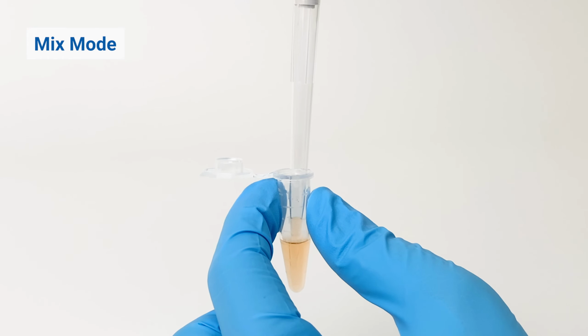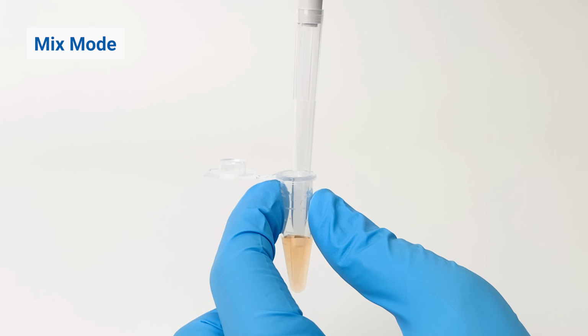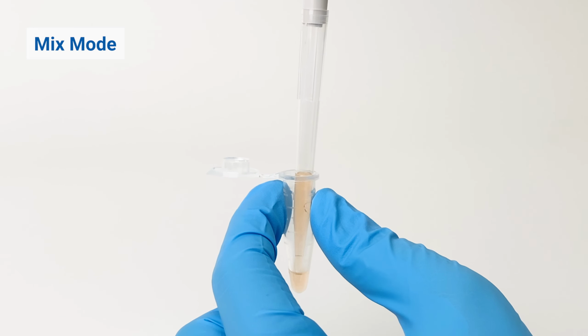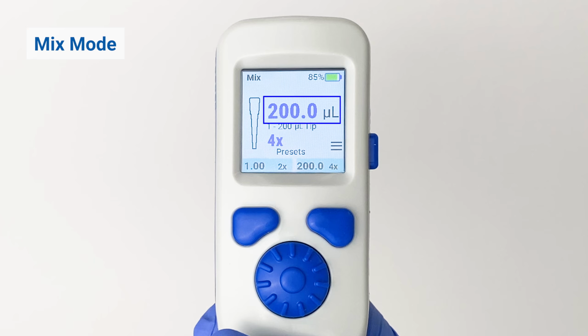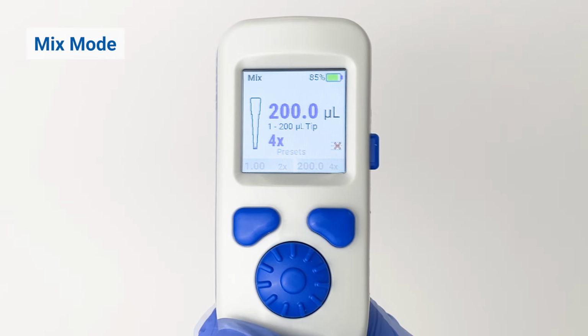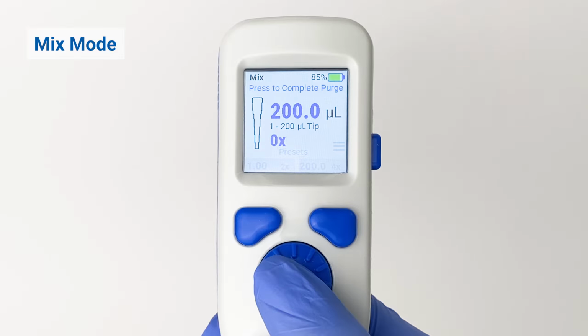Mix mode allows users to mix a selected volume by aspirating and dispensing for a determined number of mix cycles. Determine the volume that will be aspirated and dispensed with each mix cycle. Then, choose the number of mix cycles desired. Once the mix cycles are complete, if auto purge is not on, press to complete the purge.